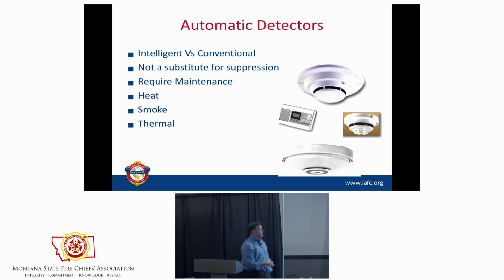So in smoke detector land, we have a lot that can happen. We have intelligent versus conventional. Conventional is smoke, go. They adjust sensitivity and they can do other things. In our new modern hospitals and buildings, they're very intelligent systems in which the fire alarm control panel goes, hey, smoke detector, you doing all right? And it says, hey, I'm good. Smoke detector 2, how you doing? I'm pretty good. Smoke detector 3, how you doing? I'm not feeling so good. It's going to say, hey, look, we've got to check this out, and it's going to send what's called a supervisory signal. Somebody's got to come check smoke detector 3. It could be getting dirty, dusty, whatever.